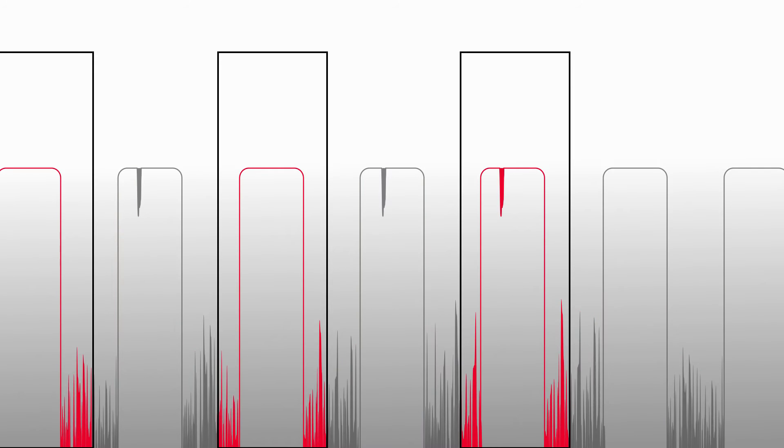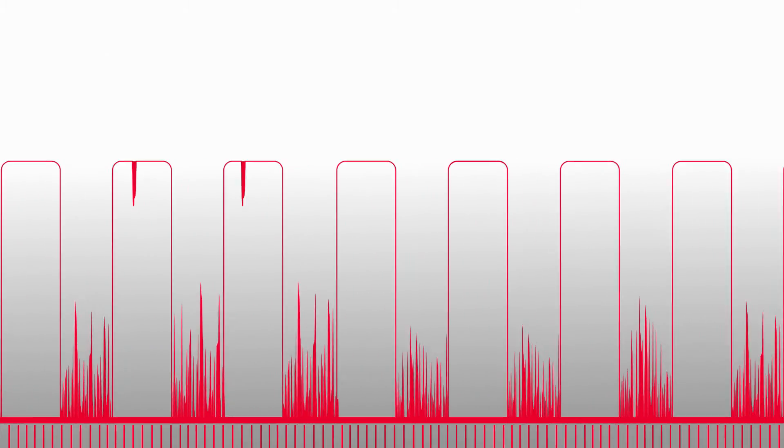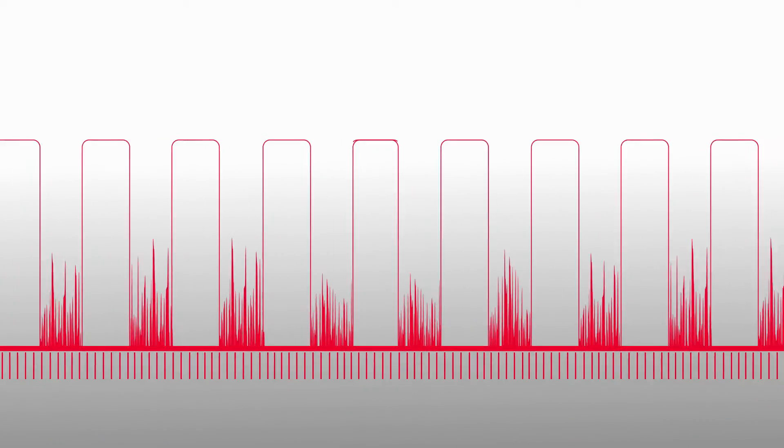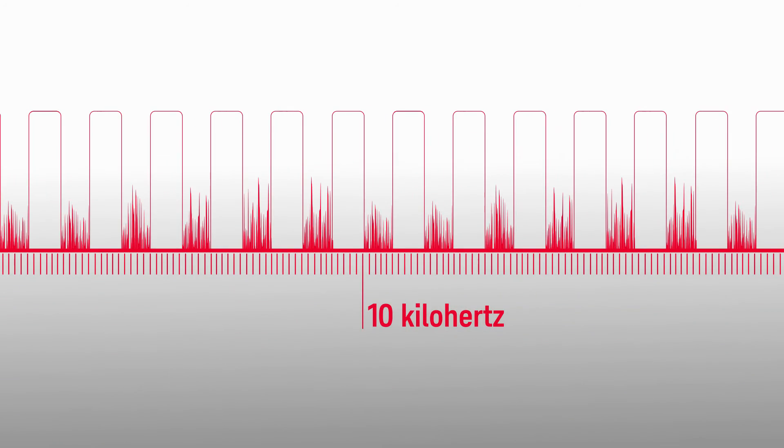Think about it. Conventional sensors only provide a snapshot of continuous pulses, leaving dead time where a glitch could slip by unnoticed. The new U2040 X-Series measures continuously, keeping pace with very fast pulses up to 10 kilohertz PRF.